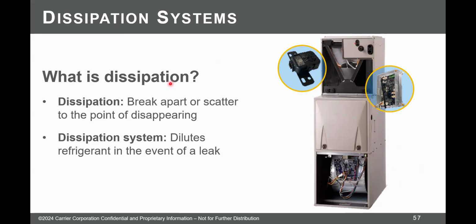All of these systems are required to have dissipation. By all these systems, I mean residential splits, commercial splits, rooftop units, mini splits, VRF, all of them have to have a dissipation system. There's like one exception to that. I'll mention that later. So the idea with the dissipation system, there's two types of dissipation. There's passive and there's active. Passive means if the refrigerant leaks, I need to have enough space for it to leak and spread into. Dissipation means it's going to spread out so far that I won't be able to actually light it.